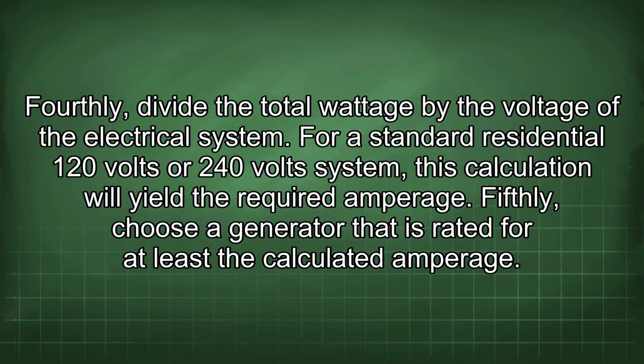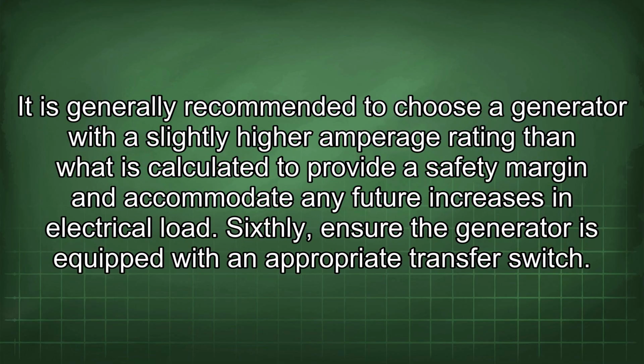Fourthly, divide the total wattage by the voltage of the electrical system. For a standard residential 120 volt or 240 volt system, this calculation will yield the required amperage. Fifthly, choose a generator that is rated for at least the calculated amperage. It is generally recommended to choose a generator with a slightly higher amperage rating than what is calculated to provide a safety margin and accommodate any future increases in electrical load.